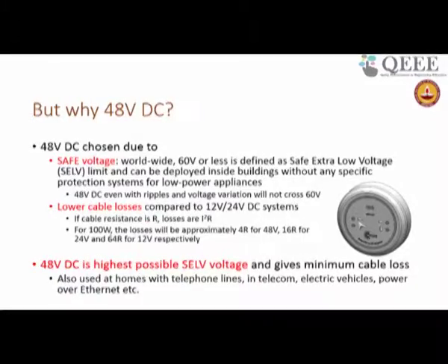Electric vehicles are standardized. All telecom systems are 48 volt DC. So it's something on which there is a sufficient amount of experience. Power over Ethernet is 48 volt. It is a best voltage, a safe voltage. If you want to do low power, up to 500 watts, which is roughly about 10 amperes, maybe up to 12, 15 amperes, this is very, very good.